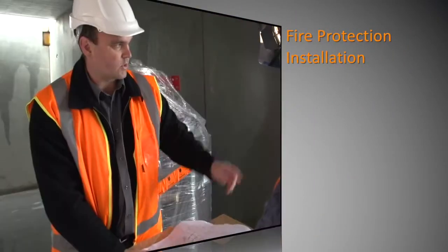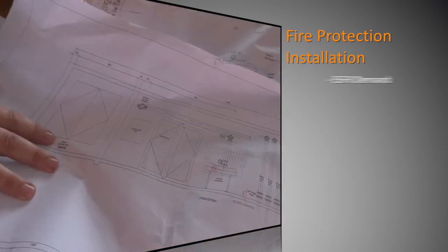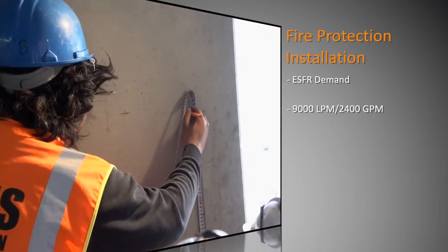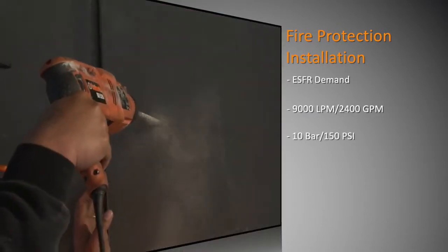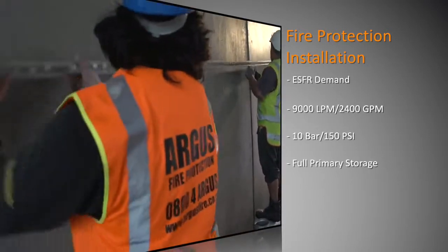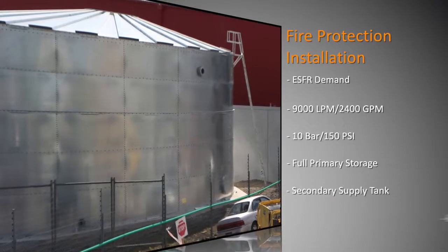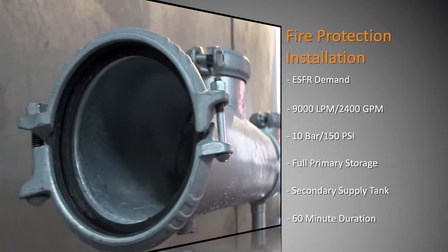The overall objective of the system we're installing is an ESFR demand of about 9,000 litres per minute at about 10 bar of pressure. We've got a full stored capacity for our primary supply, and we've got a secondary supply which is a tank with a town main infill to achieve a 60-minute duration of water supply.